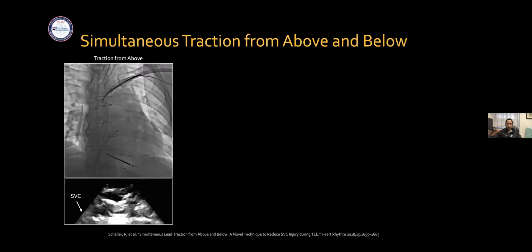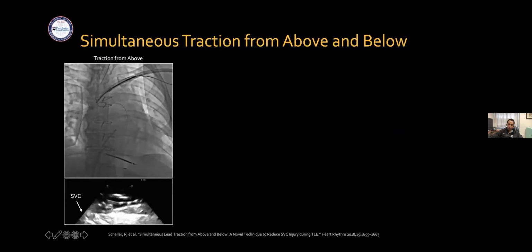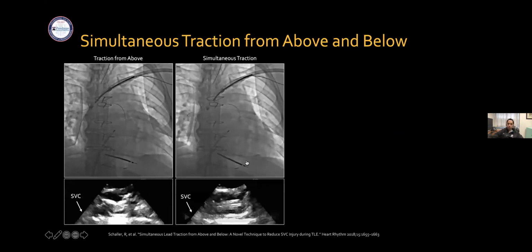And this is what it looks like when a sheath is in place. When you pull from above, look how little that lead comes off. That's because you have a stiff sheath that's stopping the lead from being pulled over. And you still are somewhat perpendicular to the SVC. And if you look locally, you can see that the sheath is actually scraping the lateral wall of the SVC, which is on the bottom here of the device. If you utilize simultaneous traction, look what happens. The lead pulls off of the SVC and it becomes much more parallel.